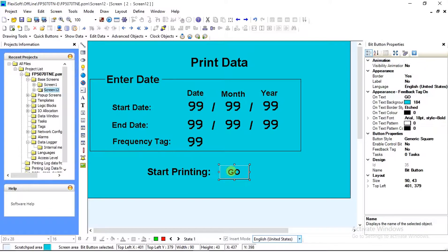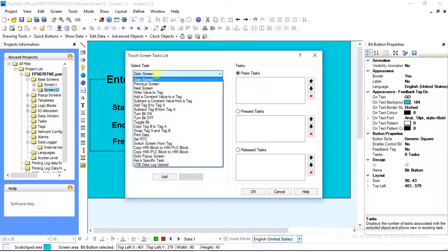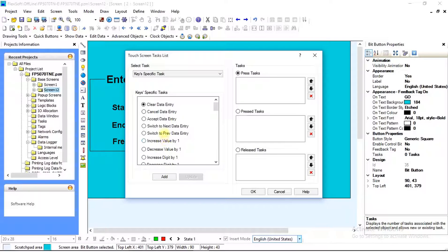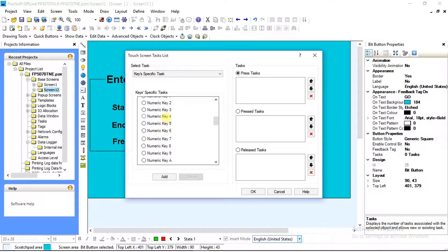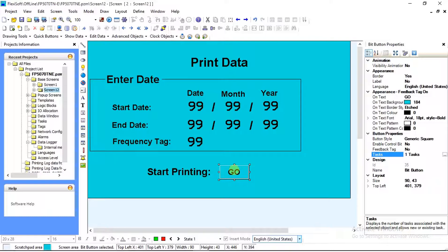Select the Go button. After selecting, you will see Bit Button Properties on the right side of your screen. In that, select Task. After selecting, the Screen Task window will open. In Task, select Press Task. After selecting Press Task, go to Select Task and choose Key Specific Task. After selecting Key Specific Task, multiple options become available. Select Start Printing of Group option — we will select Group 1 because in the data logger we defined Group 1. In Port, we will select 1 because the serial printer is defined on COM1. You can do the same for Stop Printing. After all settings, click Add — it will get added in Press Task — then click OK.